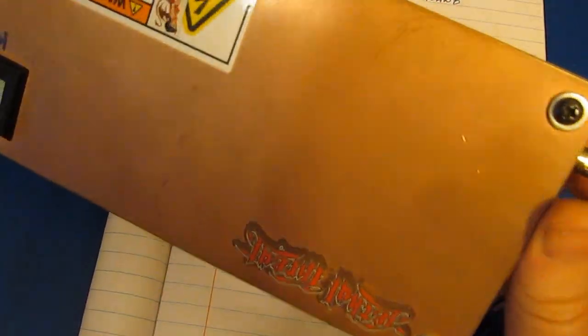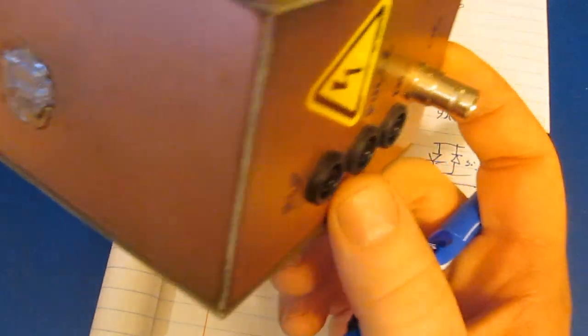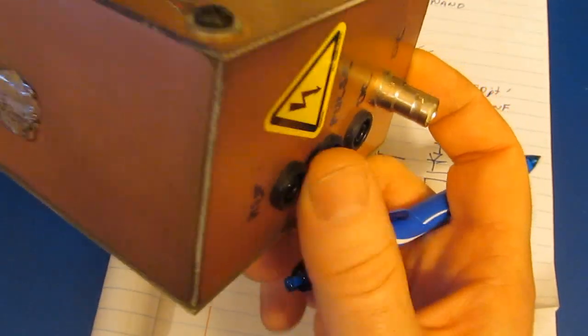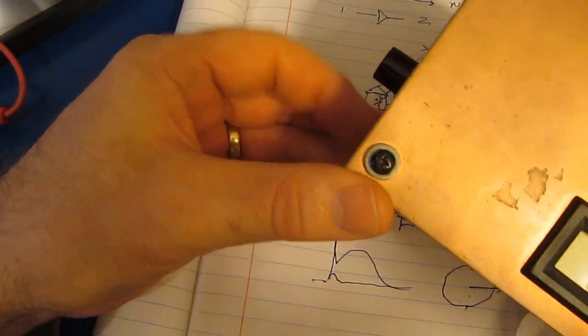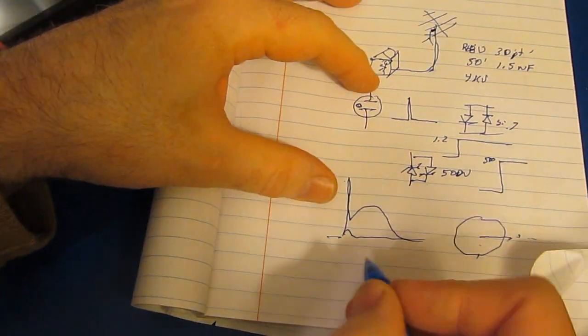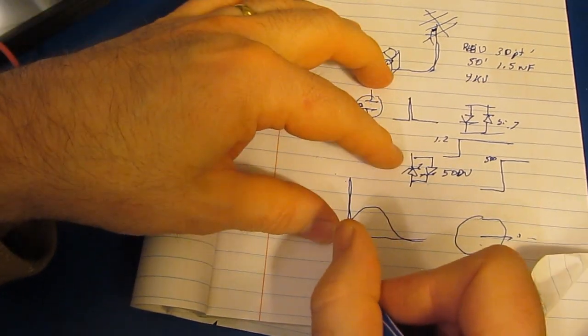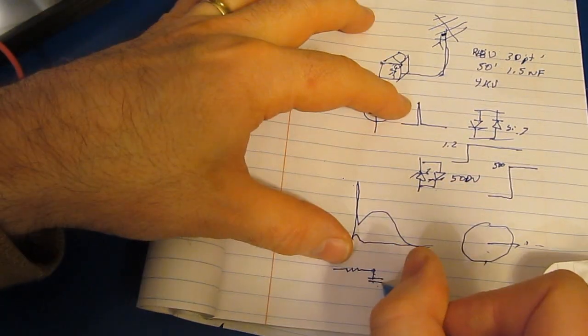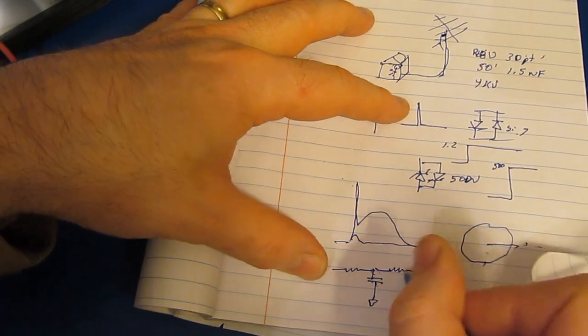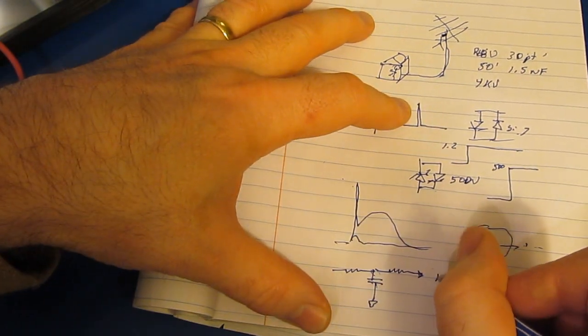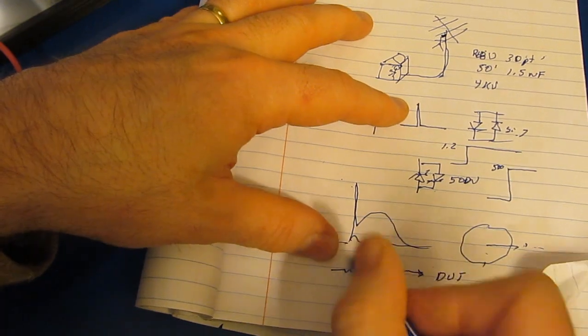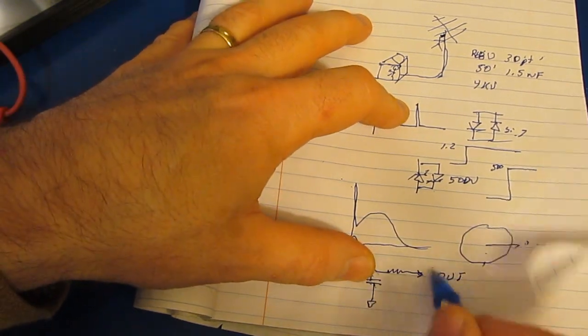This generator pretty much follows the IEC standard. I can attach the device I want to test to the ports here, and manually trigger it with a button on the side, flipping the leads to do both positive and negative transients. The problem with using that generator is I'm using the human body model. Essentially what you end up with is a capacitor with some source impedance, going off to our device under test. I charge this thing up to some voltage, and then discharge it through my device.